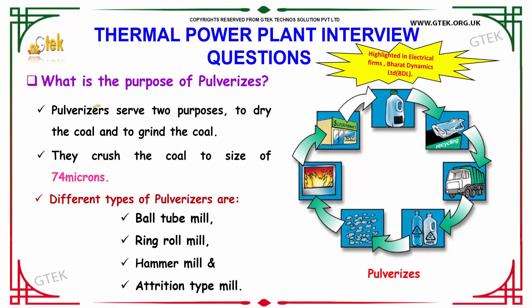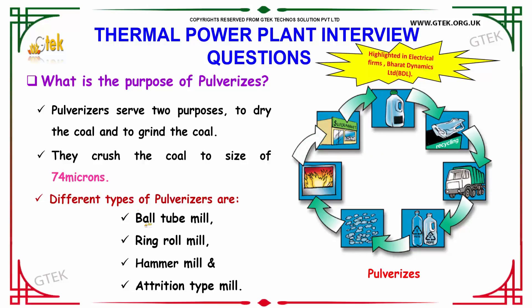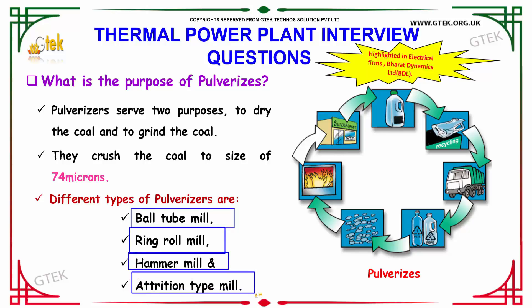What is the purpose of a pulverizer? The pulverizer serves two purposes: to dry the coal and to grind the coal. They crush coal to a size of 74 microns. Different types of pulverizers available are ball tube mill, ring and ball mill, hammer mill, and the attrition type mill.